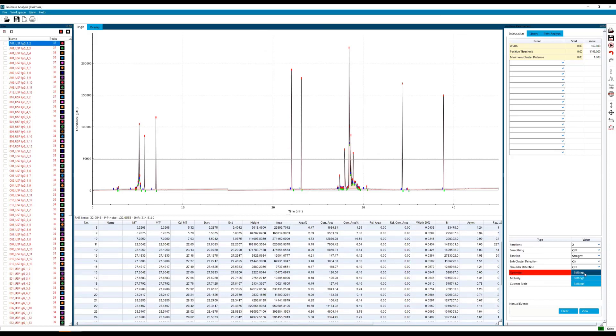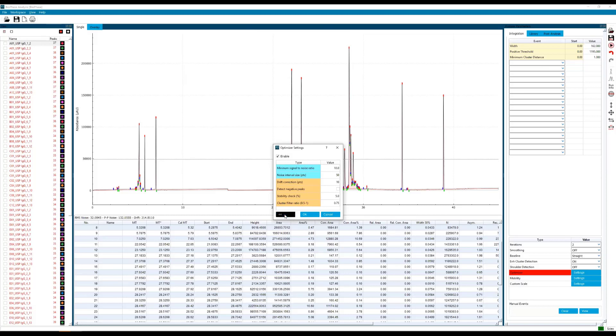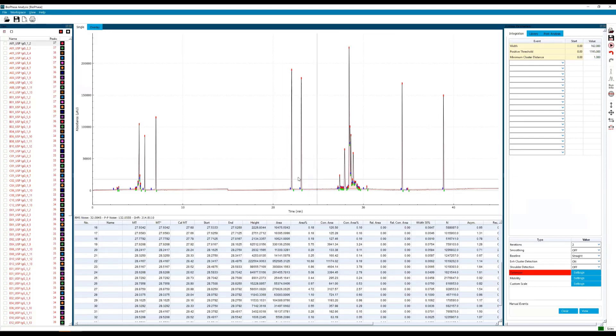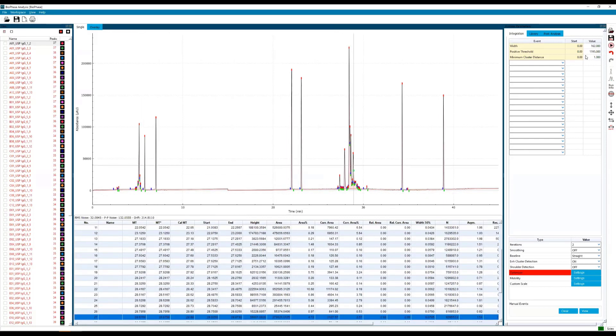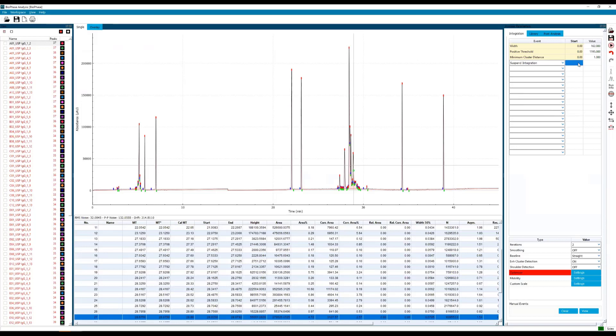You're going to run your sample, run your plate, you're going to have a lot of data to analyze. One of the things where you might start is with what we call the optimizer down here. So we go ahead and enable this. What the optimizer is going to do is it's going to try and figure out where a true baseline is based on this minimum signal noise ratio of 10, noise interval, and also these other parameters that I don't personally change much. Our minimum signal noise ratio of 10 is our limit of quantitation. You go ahead and click OK there. And then we can click this little play button that's analyze.